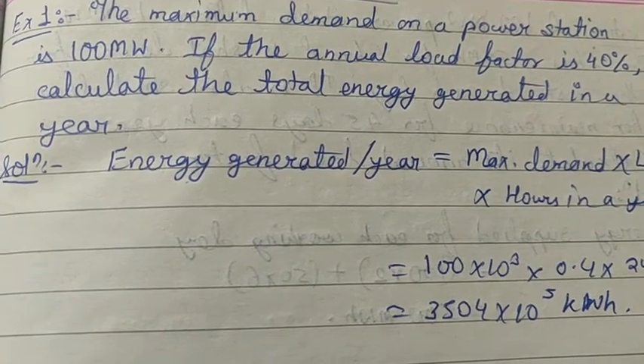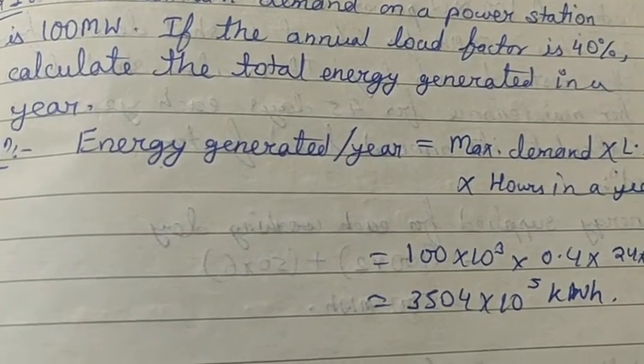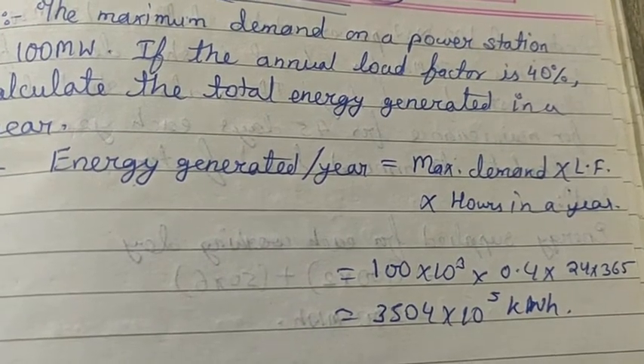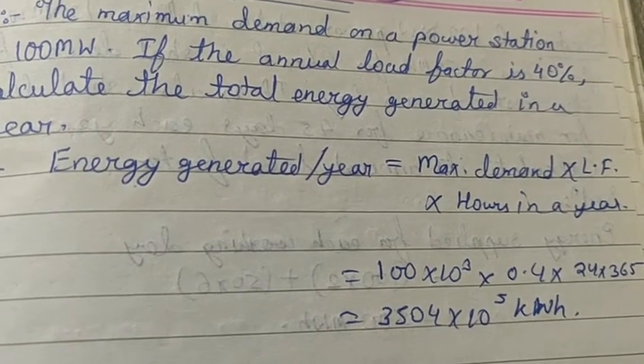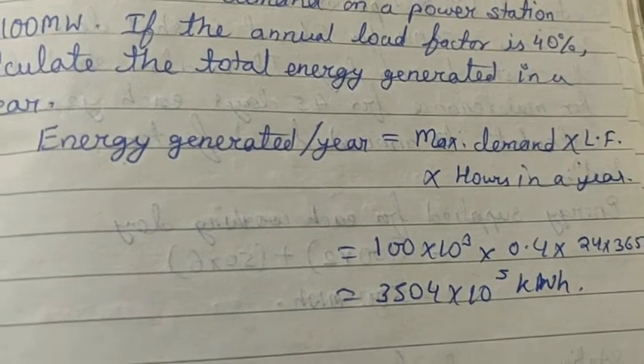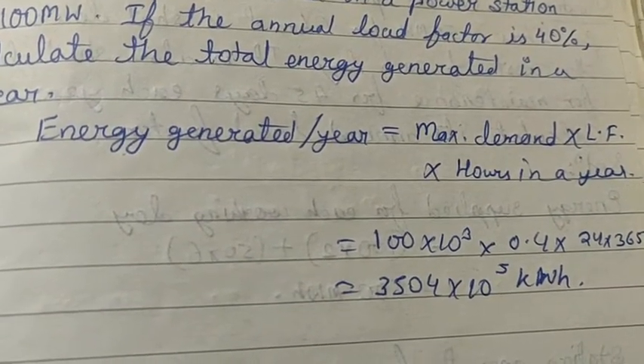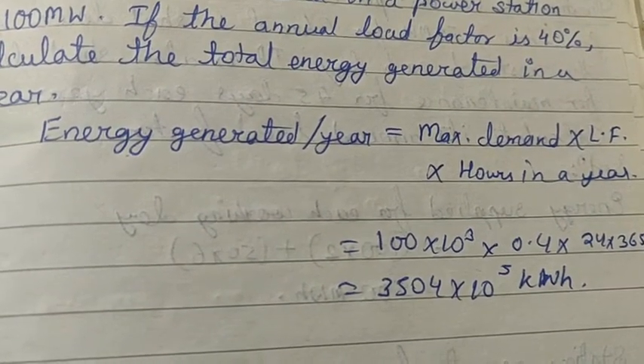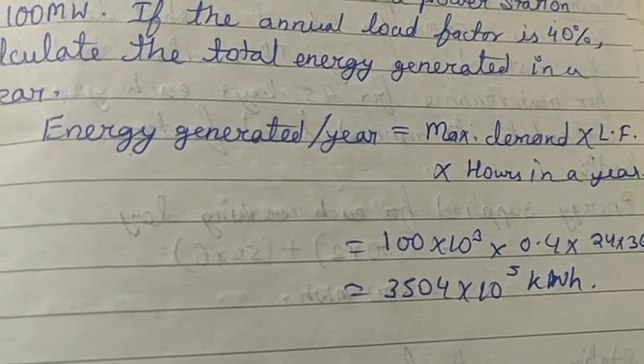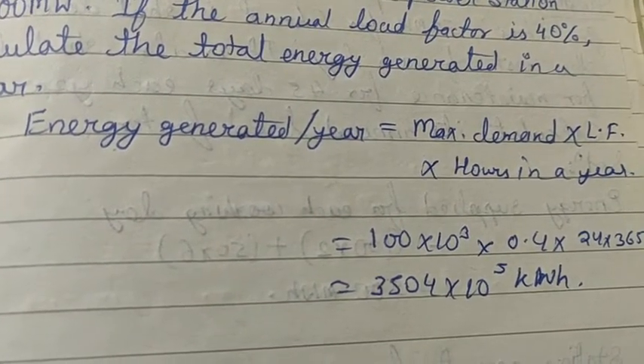Total energy generated in a year — the formula is: maximum demand × load factor of that power plant × hours in a year. In one year, there are 24 hours in a day and 365 days, so 24 × 365 gives the total hours in a year.